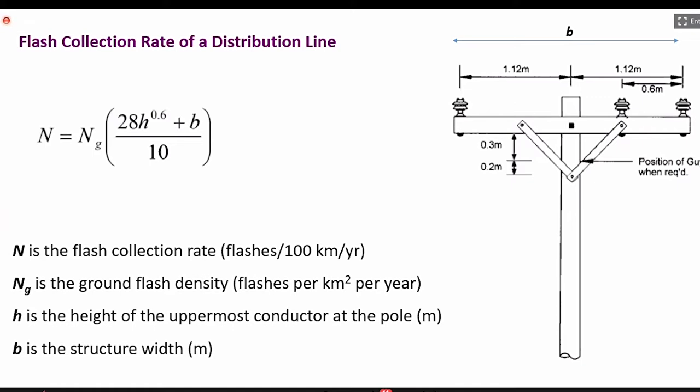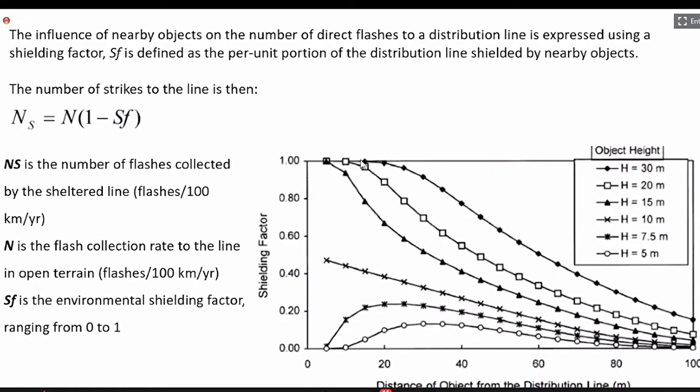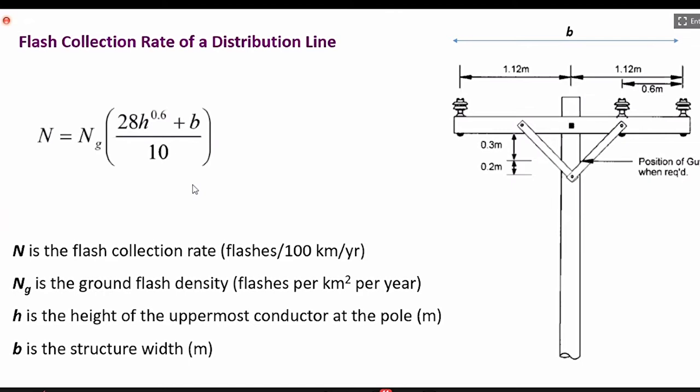If the country has a low ground flash density, or NG, this value will be in the order of say 2, 3, 4 flashes per square kilometer per year. If it is around 6, 7, 8, then it is medium. If it goes to like 10, 12, 13, then we say it is quite high.